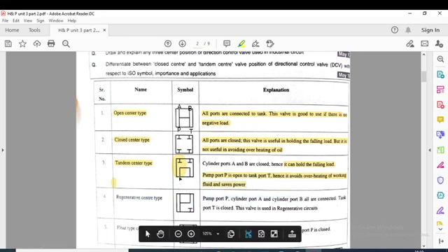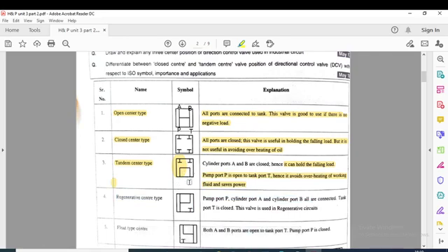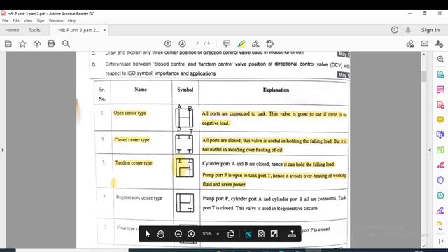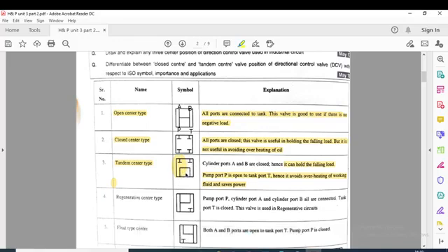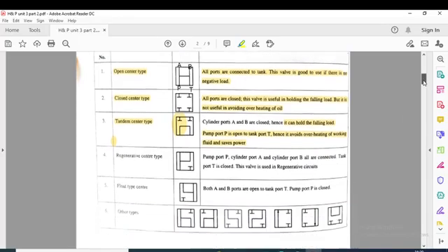Here what happens? The pump port P is directly connected to the tank port T, then high pressure will not develop inside this circuit, and as this actuator is in idle position, no supply of oil to the actuator is needed. So the pump directly supplies the oil to the tank, so no high pressure is developed here, and as there is no high pressure, no temperature rise occurs, and the pump keeps pumping the fluid at low pressure, so no pump power is required there.